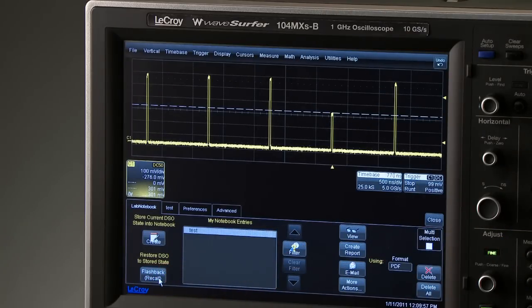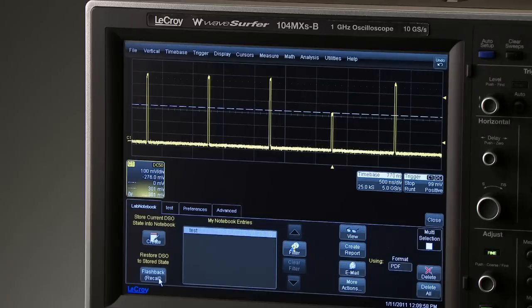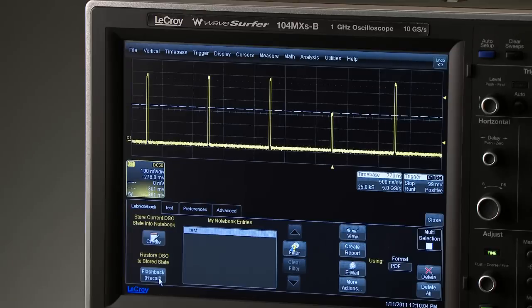At a later date, even after oscilloscope settings have been changed, the flashback will always recall the settings from when the report was saved, enabling easy comparisons between measurements made at different times.